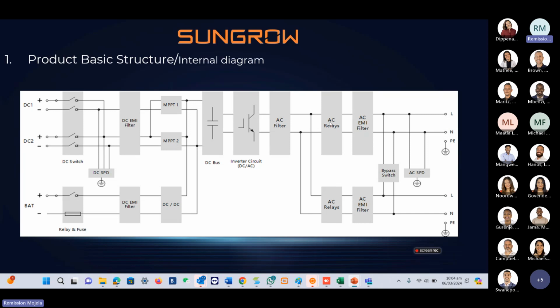But the moment the grid falls off, both these relays, the AC relay and the bypass, open, and then power now flows through the AC relay to the AC EMI filter and then to the backup loads. So one important thing is, with all our devices, we have a pass-through except for the 6RS. So the 6RS under grid operation, the backup port still only connects 6 kilowatt. But with the 10, you can connect up to 14.5 kilowatt. And then with the 15, if I'm not mistaken, is around 33, and with the 25T is around 43. So the other devices do have a pass-through except for the 6 kilowatt. Just remember that even when you check from the data sheet, you'll be able to see that all the other devices do have a pass-through except for the 6 kilowatt.